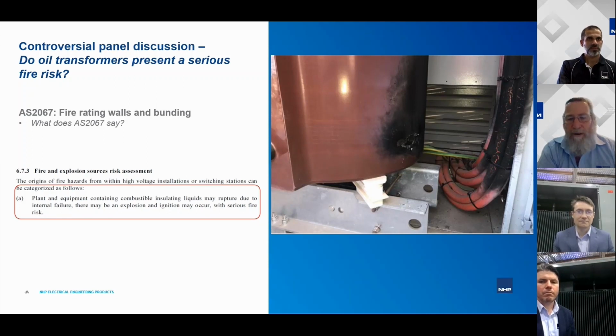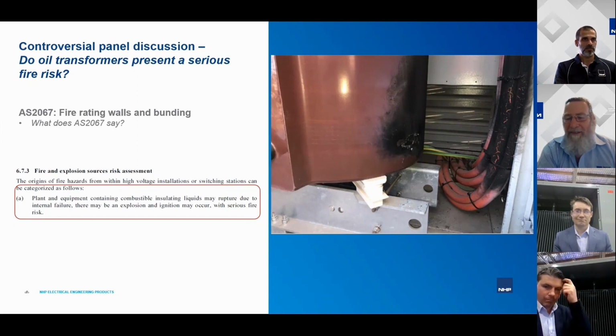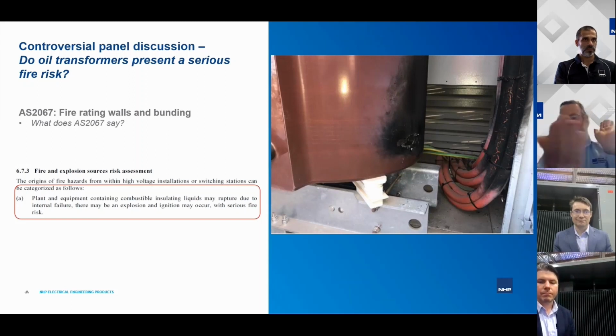And an example, a very extreme one, I have to admit, but a number of years ago, there was, I think from memory, an 800 to about 1,000 kVA wind farm transformer. And it had been noted over a period of time that one of the HV A-type bushing wells was leaking. And it was noted that at some stage they needed to carry out some maintenance. Unfortunately, what happened is the oil level actually dropped below the top of the tap switch, dropped below the top of the bushings, and there was quite a catastrophic arcing event, split the tank open. And yeah, the photos were quite horrendous. Literally a tank with all four sides split open, a burnt out core coil assembly sitting in the middle of a paddock. You know, very, very extreme.